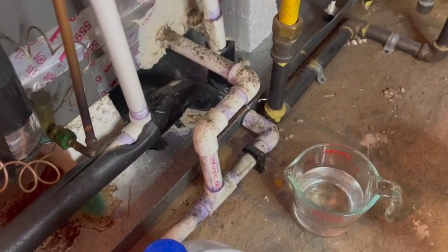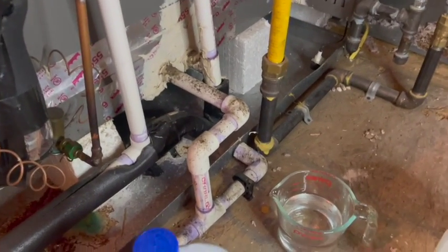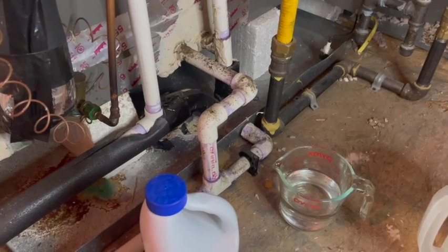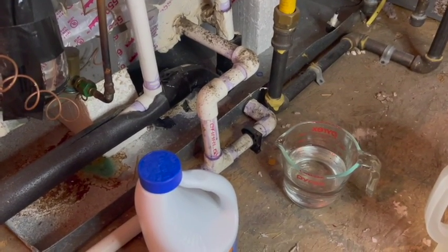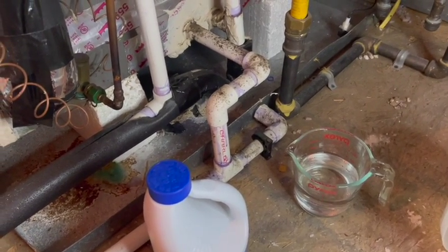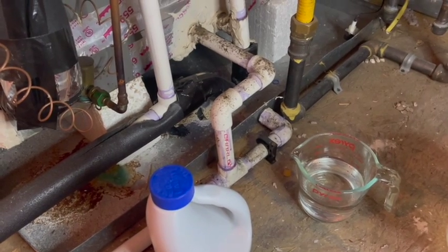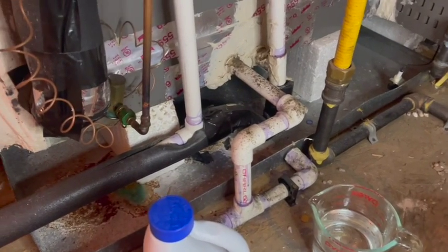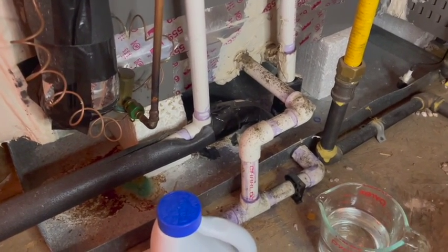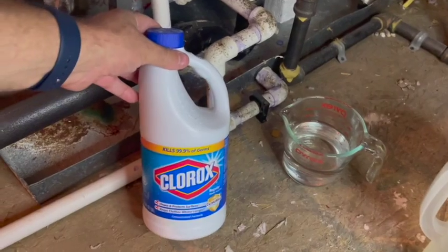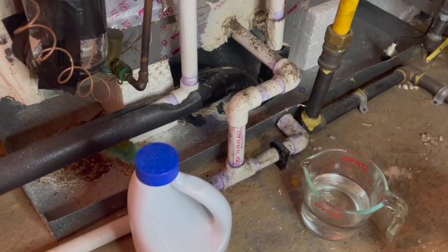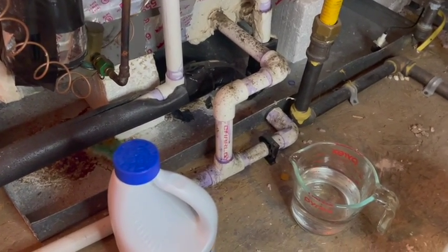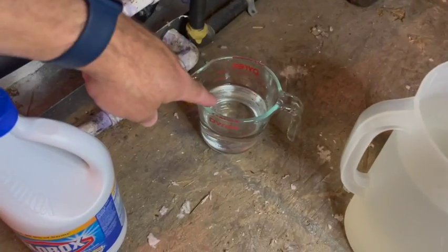Okay, now that we confirmed that the primary drain is underneath the master bathroom lav sink and the secondary drain is on the exterior of the structure over that window near the back of the house. So we know to flush the primary, we can use Clorox, a bleach solution, 1/4 cup of bleach to 1 cup of warm water. That's what I have in here.